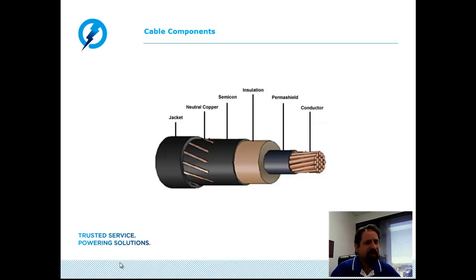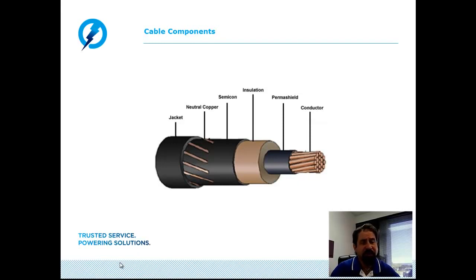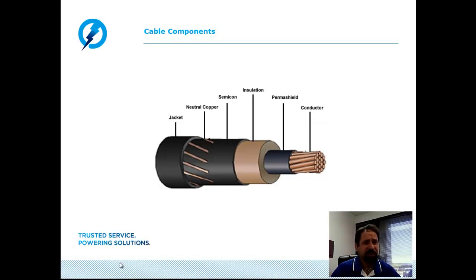In a typical medium voltage cable, copper and or aluminum wires — stranded and or solid — are used as the conductors. These conductors are covered with an extruded polymeric stress control layer made of semi-conductive compounds, often referred to as the perma shield, strand shield, or conductor shield. The insulation layer immediately surrounds and is fully bonded with the conductor shield. An insulation shield encases the insulation, and the copper neutral wires are wound around it, usually covered with a thermoplastic polyethylene jacket for mechanical protection and to reduce moisture intrusion, which can cause premature cable failure.